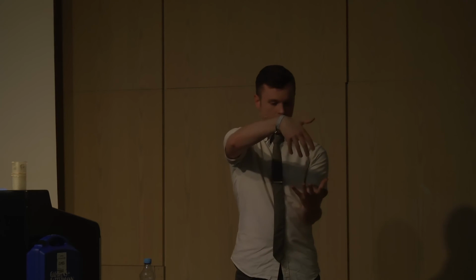One of the difficult things about soft sensors is it's difficult to compensate for the flex of the system when calculating how much force is on it, because you can picture if you made a flat sensor array and you wanted to detect how much pressure a person, say a person with an amputation, residual limb is inside of a socket, you're trying to measure where the pressure is. So you have a flat sheet of sensors, and you stuff that into the socket, and the person stands on it. The sensor array is actually going to be detecting a lot of forces because of the particular order in which it bent, not directly because of the amount of pressure that it's experiencing.